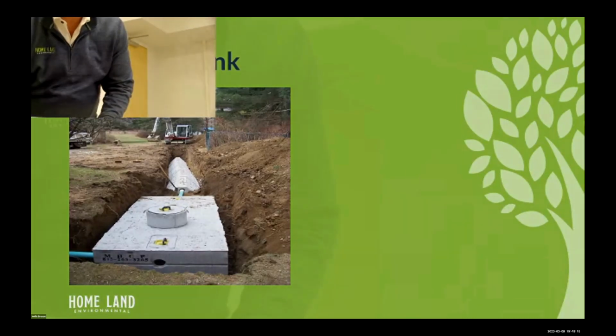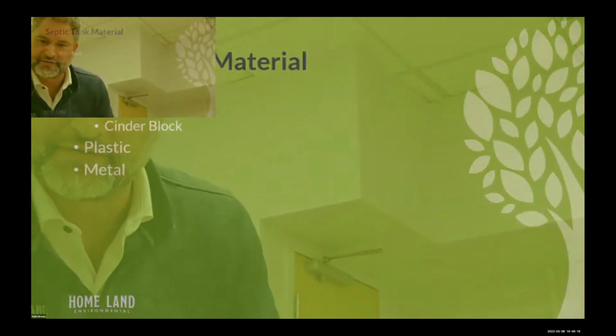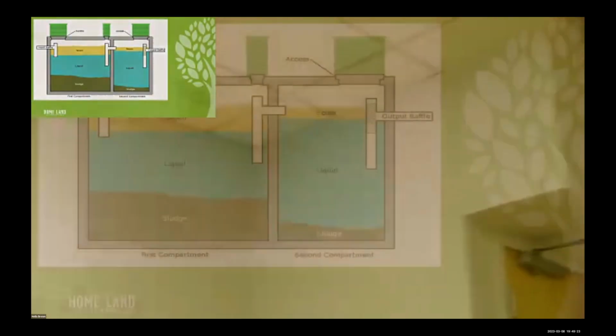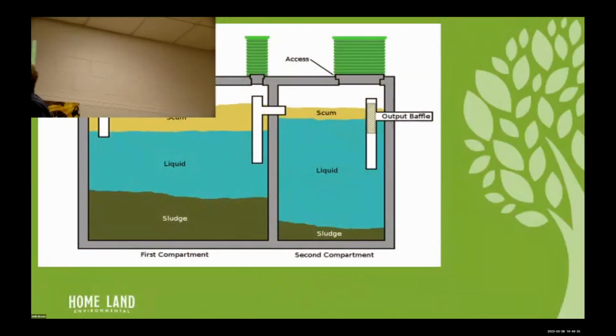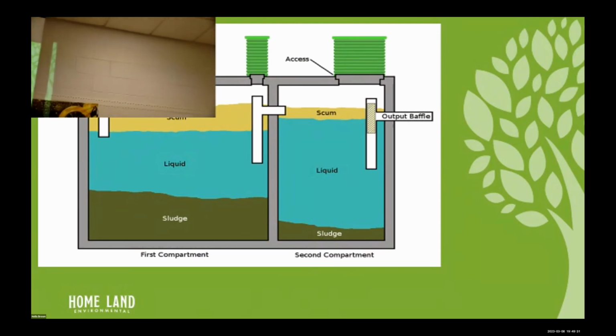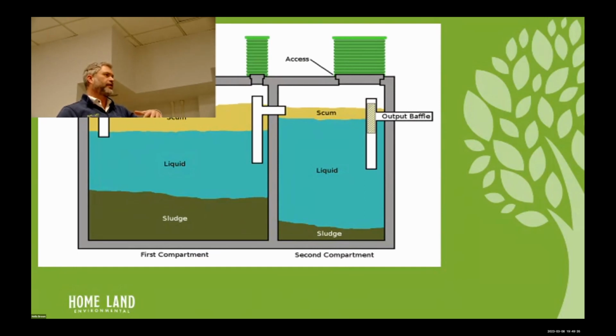The great part about that is if it happens to leak, in other words, if they didn't do a very good job with the tar, well, the seam's up here, so no water's going to leak out of that because the seam is above the water level. So if they didn't do that install right, which is basically sealing the lid to the tank itself, you could have some groundwater intrusion come into that tank in high water table areas, like the Eastern Shore, but we don't have to worry about the water in the tank leaking out.